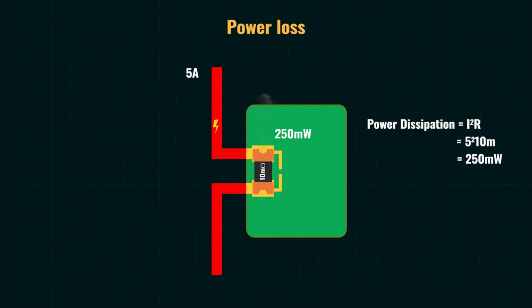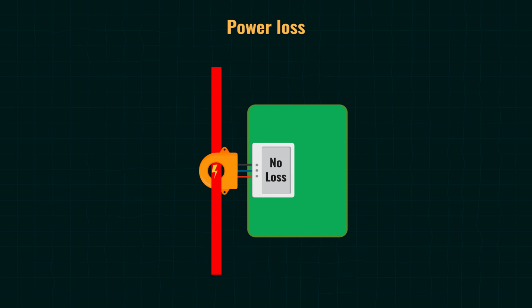Next up is power loss. One drawback of shunt-based sensing is power loss. Even though the shunt resistor is tiny, it is still in the path of the main current. At high current, it can generate heat and waste power. Hall effect sensors avoid this completely. Since the sensor doesn't touch the current path, there's zero insertion loss, which means no wasted power due to the sensor itself.